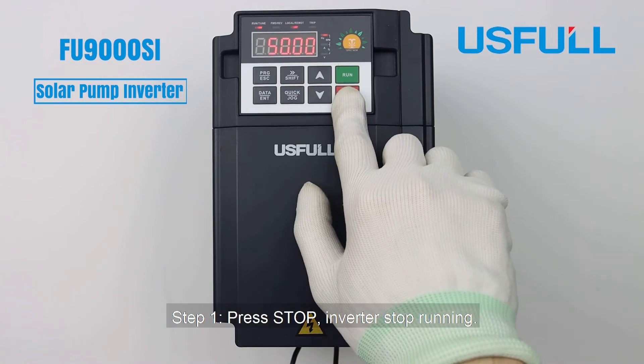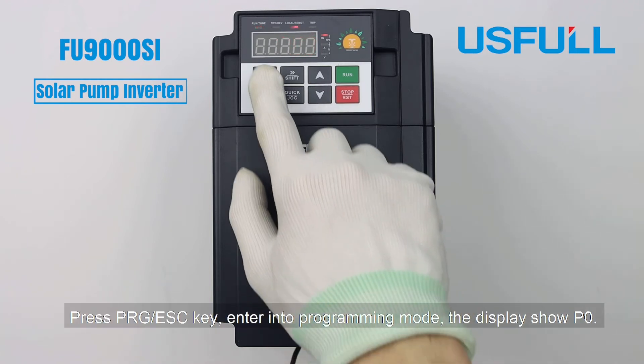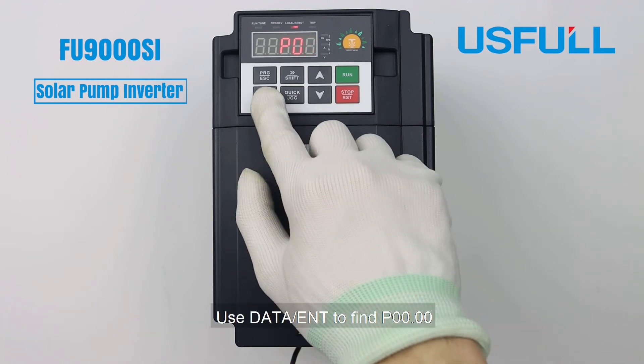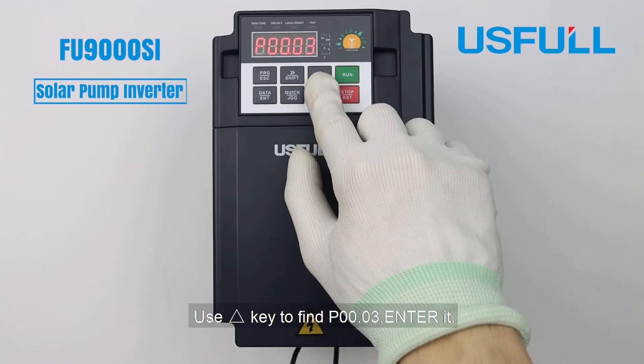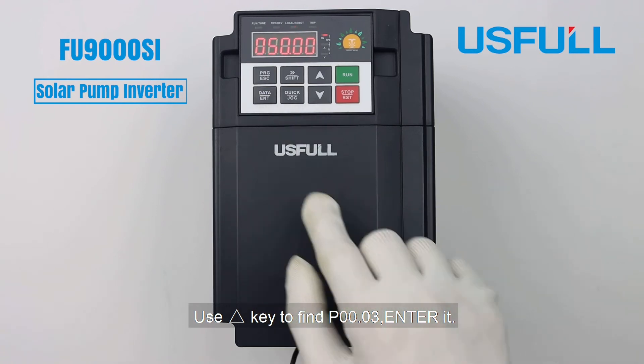Step one: press Stop so the inverter stops running. Then press PRG to enter programming mode. The display shows P0. Use the DATA/ENT key to find P00.00, then use the Up key to find P00.03 and enter it.